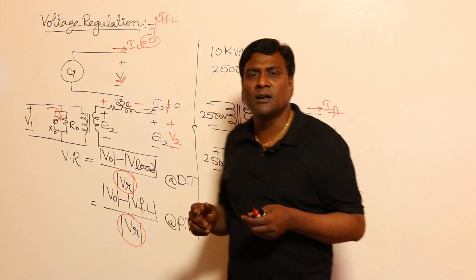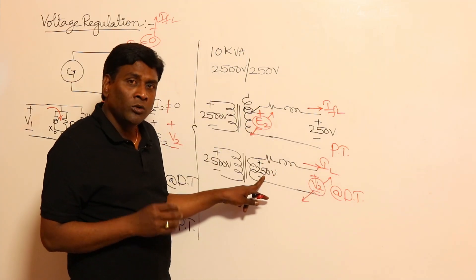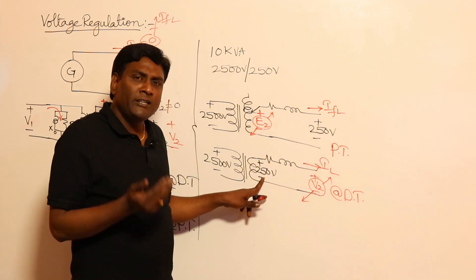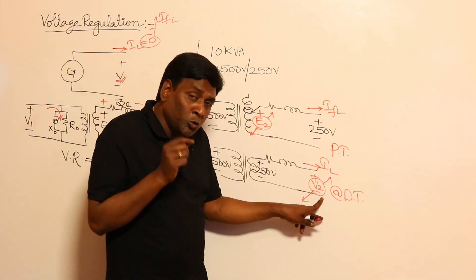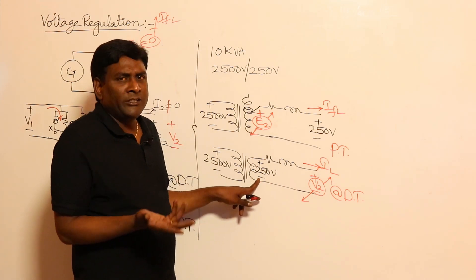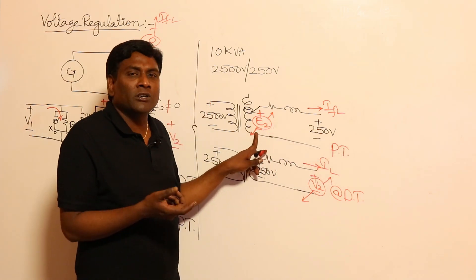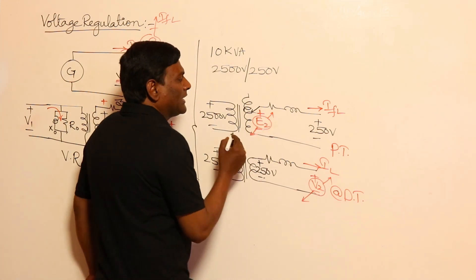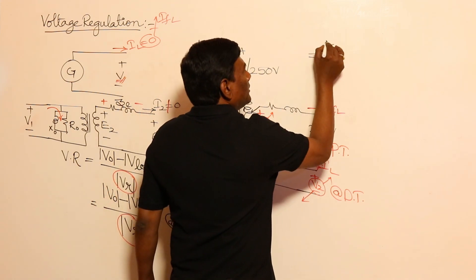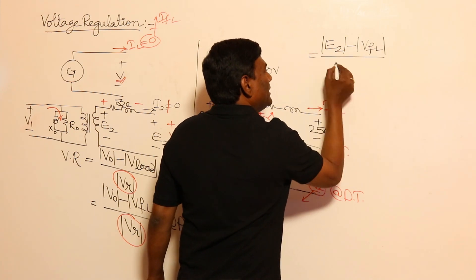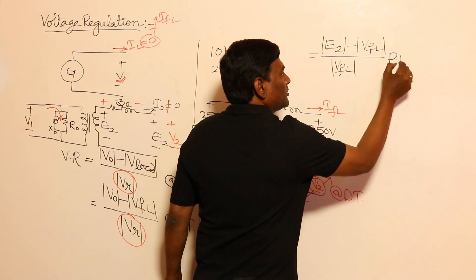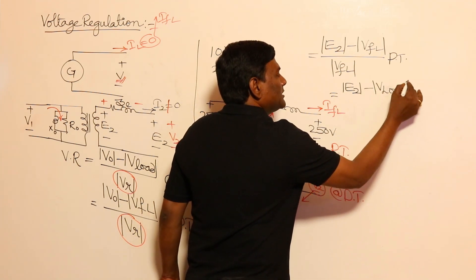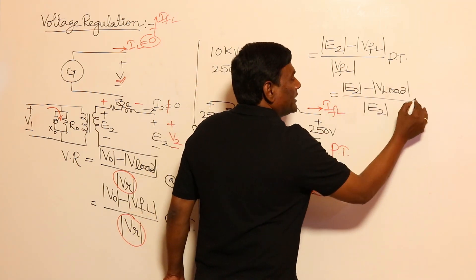For a power transformer, voltage regulation equals (E2 − V_fullload) / V_fullload × 100%. For a distribution transformer, voltage regulation equals (E2 − V2) / E2, where E2 is the no-load voltage and V2 is the any-load voltage. Because for a distribution transformer, the no-load voltage E2 is given and the rated terminal voltage varies with load.